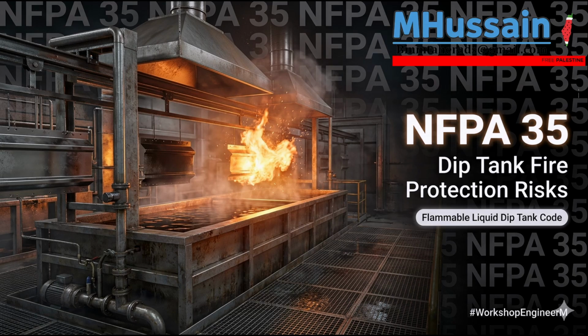Because the simple metal-on-concrete friction of a sliding barrel generates localized heat at the bottom of the drum. And that localized heat transfers through the thin seal wall and can instantly ignite the highly sensitive nitrocellulose inside. Just from sliding it. Yes. The standard dictates that drums can only be moved by rolling them on their lower chime, the reinforced elevated rim at the base of the drum, which minimizes contact area.